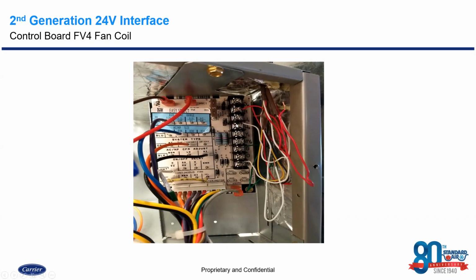Okay, so the W2 terminal from the thermostat, when it's set up as a 2 heat, 1 cool option, you want to wire W2 directly to this easy select printed circuit board so that when that time comes that we need to kick on that backup electric heat, it'll send the control signal directly to this printed circuit board and the electric heat will come on. Now you can set the threshold of when the electric heat comes on and comes off from your third-party thermostat. Now, of course, each third-party thermostat is a little bit different as far as adjustable ranges that you can have between there, but typically about 2 to 3 degrees is usually what we see for a threshold when the heat pump's running and it's not keeping up when we need to kick on that electric heat during colder ambience. Okay, and then finally you can see on here you have your G terminal wired up, and that's coming from G1 from the 24-volt interface.